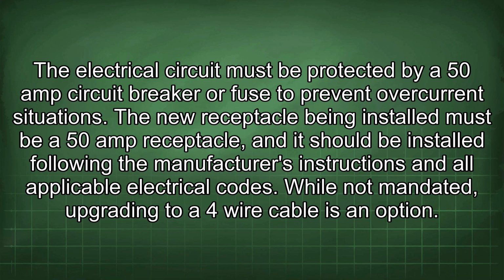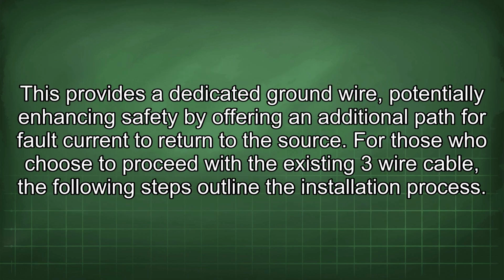The new receptacle being installed must be a 50-amp receptacle, and it should be installed following the manufacturer's instructions and all applicable electrical codes. While not mandated, upgrading to a 4-wire cable is an option. This provides a dedicated ground wire, potentially enhancing safety by offering an additional path for fault current to return to the source. For those who choose to proceed with the existing 3-wire cable, the following steps outline the installation process.